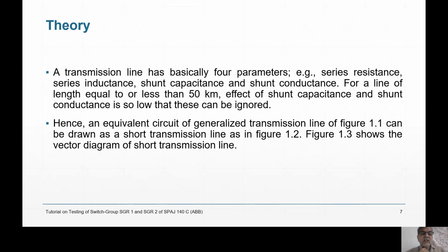For a line of length equal to or less than 50 kilometers, the effect of shunt capacitance and shunt conductance is so low that this can be ignored. So for analysis, we have to do something: we divide the transmission line into 3 parts. Short transmission line is less than 50 kilometers, medium transmission line is more than 50 kilometers.